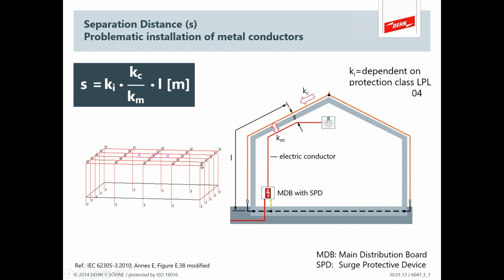And remember, the IEC methods give you higher current ratings, which would impose more separation. That's one of the reasons the IEC methods are somewhat better than NFPA, because we can be more diligent and expect a higher lightning current. We can also expect that we need more separation. There are a lot of discussion points about this, even a slide like this where you can talk about what's bonded, what's not bonded, what's separated. But separation distance is one of your pillars. If you disregard it, you will have poor results.